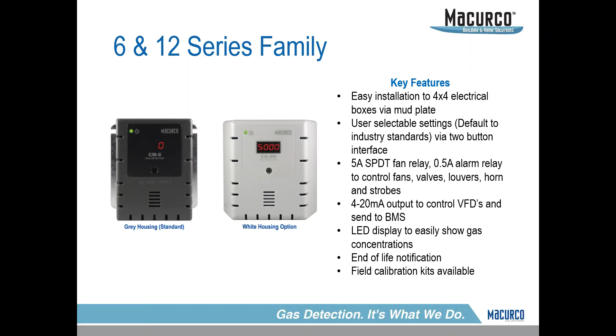All these detectors are configurable. They're set to OSHA standards. We get the question all the time, is it UL 2034 or UL 2075? UL 2075 is in this line, yes, for the CM6, which is our carbon monoxide version. However, when you get to a short-term sensor life of 2 to 3 years, the 2075 doesn't apply. They look for longer sensor lives there. And the 2034 listing is more for a residential listing, so it's a time-weighted average basis. You do not want to have a time-weighted average basis in a commercial environment, a boiler room, or a garage. That would just cause some serious life safety implications.